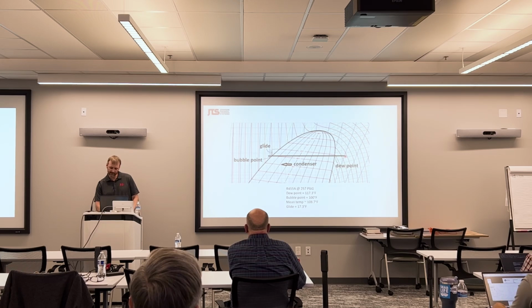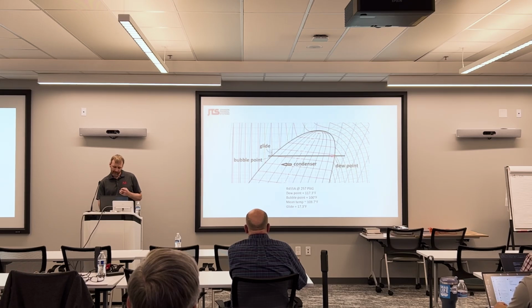As discharge gas enters a condenser, you've got this first leg over here on the far right. This is known as the desuperheating. It's stripping heat out of the vapor, but we haven't yet condensed. Once you cool the temperature to a point where we hit the saturation curve, you hit the dew point for the refrigerant, and that's where we have 100% saturated vapor. As that refrigerant travels through the condenser coil, we're actually changing temperature as our liquid becomes more and more concentrated in the coil. If you notice, at the end of the coil, at the bubble point, we've got a very different temperature than at the dew point.